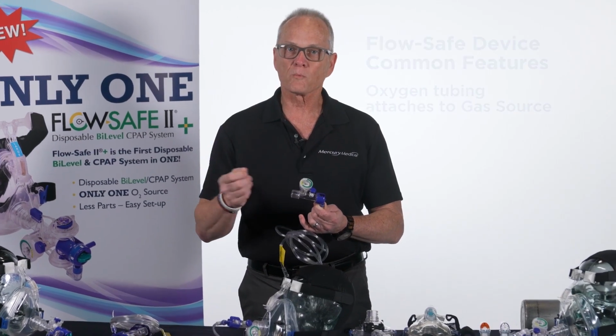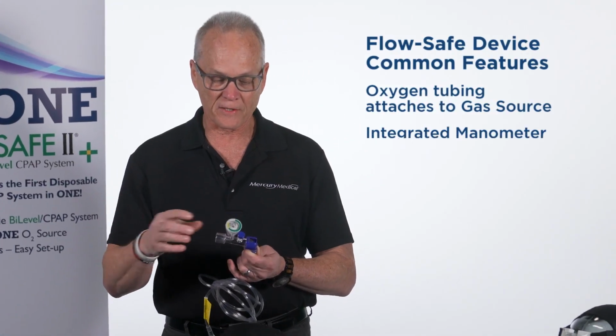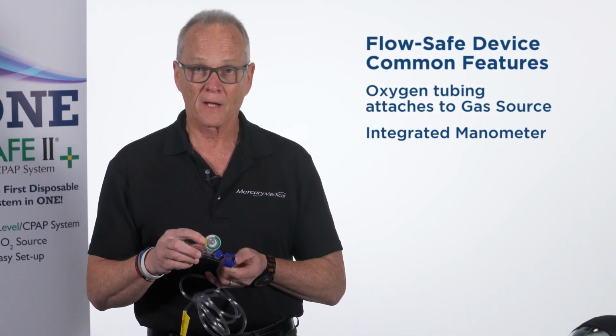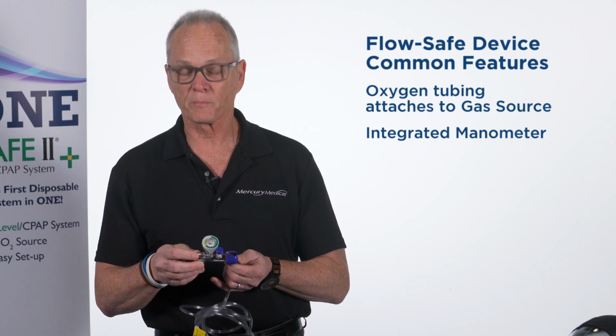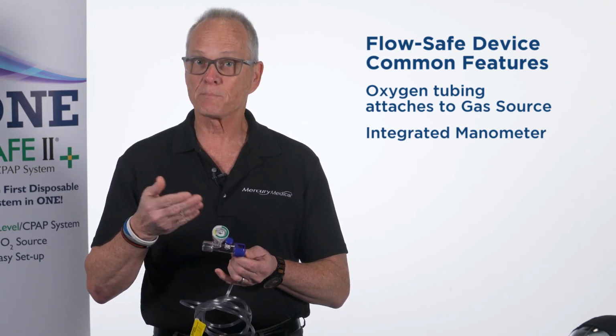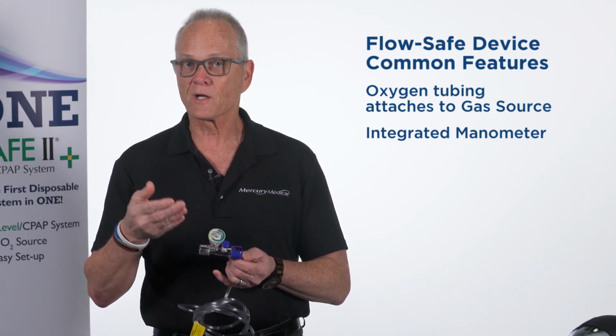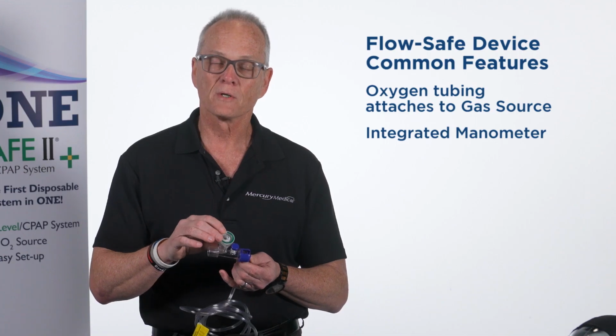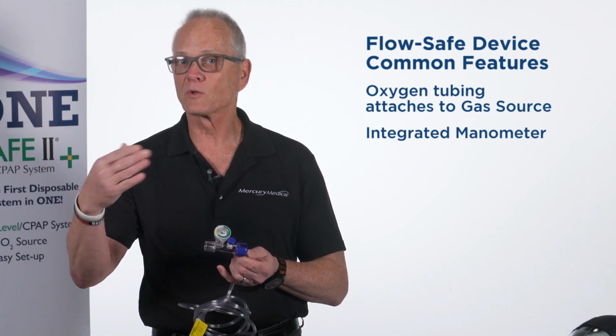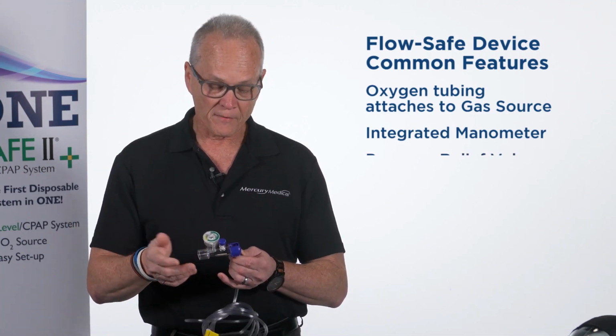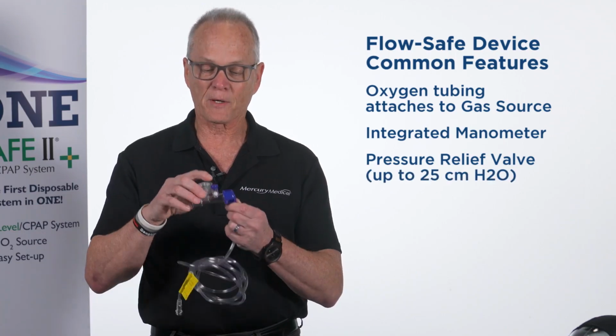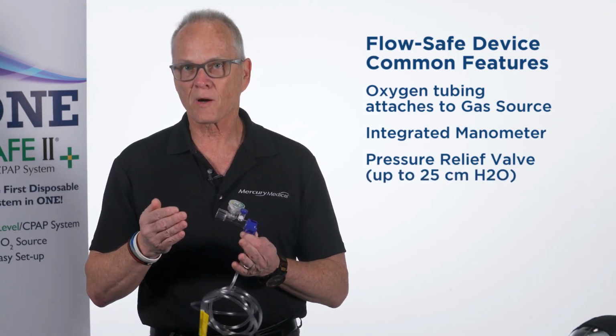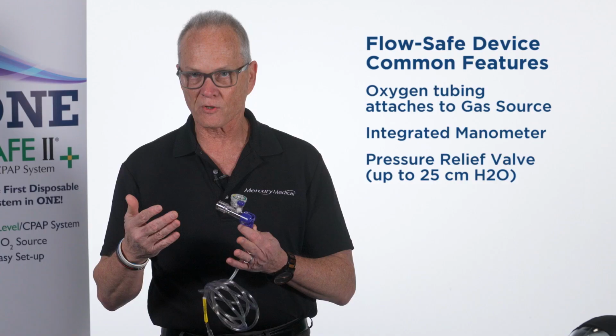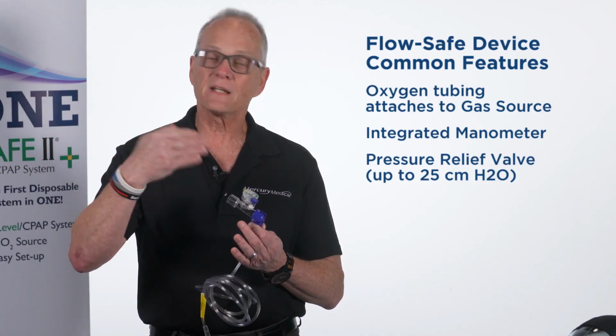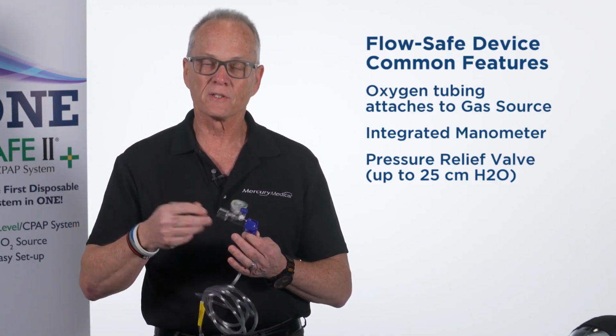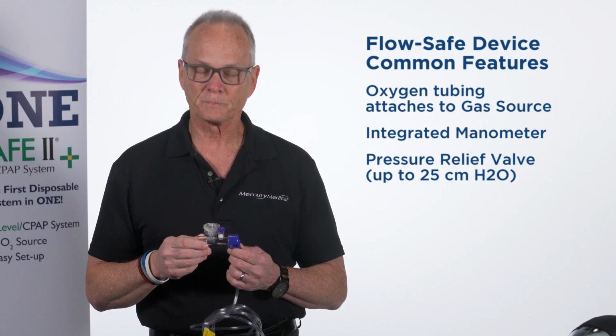The other thing that's incorporated in all versions of FlowSafe is an integrated manometer. I, for one, as a clinician, would never want to put somebody on an airway pressure that I could not only document, but also see what that pressure is. I'm going to expand a little bit on that as we work through this. The other thing that they all have is a pressure pop-off valve. A pressure pop-off valve is more of a safety feature that allows, if there's any excessive pressure, it to be vented so that we're not causing any harm.